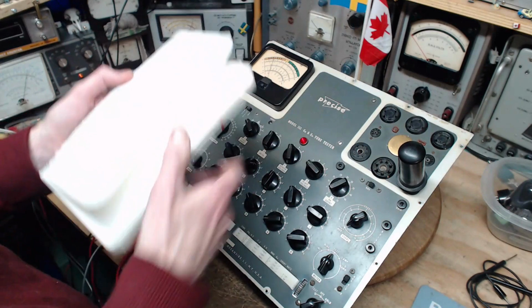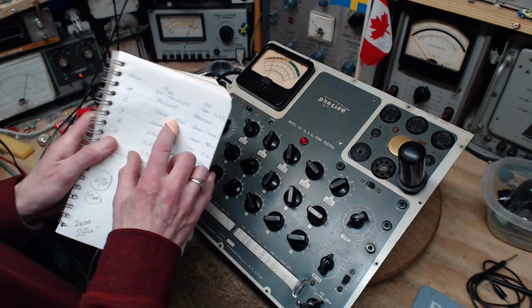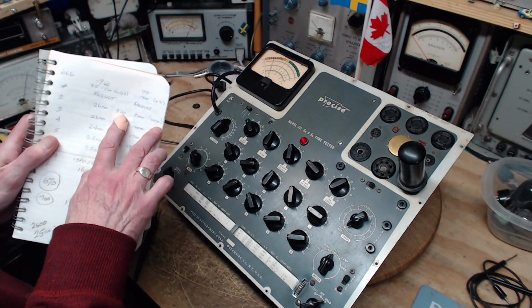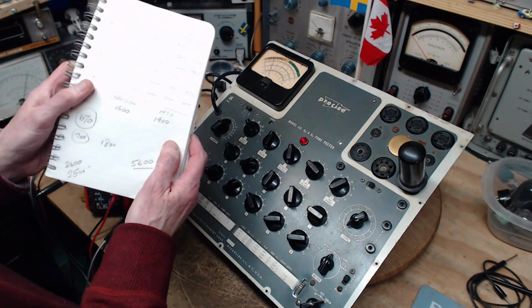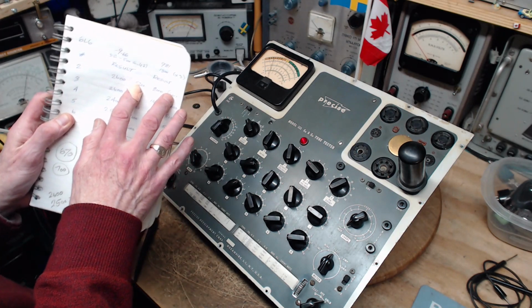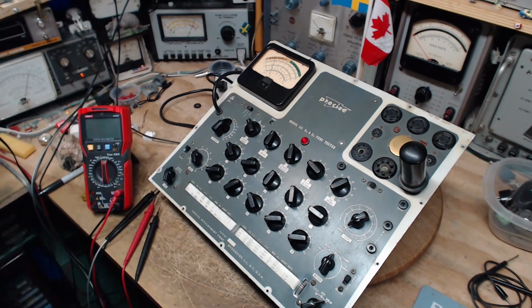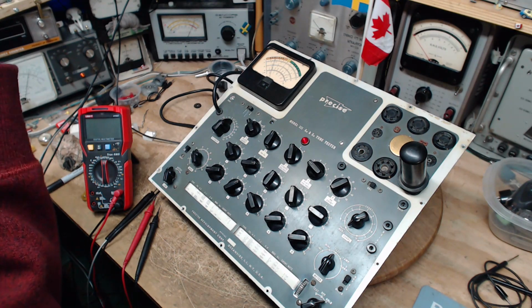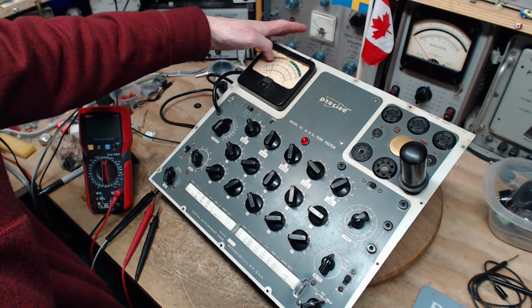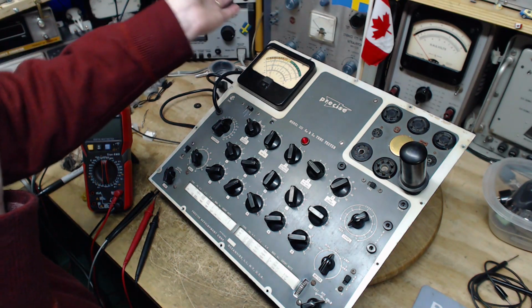Tested this tube quite a bit. Take a look at the previous readings. This is tube number 2, isn't it? Yes, tube number 2. So 5,200 and 6,000 in two other testers, as compared to this one, which is saying 4,000. Well, we're getting closer, but this isn't nearly as far off as the other one, is it? I don't know. And what's the reject point? You can't compare these things directly. So the reject point is 3825. So I'm actually in the good by a small percentage.